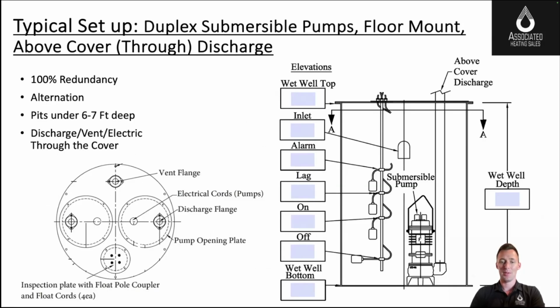Okay. The only other thing I'd like to point out is how these pumps sit. So this is going to be a floor mounted pump with a vertical discharge that's sort of installed on the pump. So when you go to remove this pump, you're removing the pump with a chain up through the pump opening here, and you have a discharge pipe that's quite long that's attached. So this gets us into when we need a rail system. If this pit is deep and we're indoors, so let's say it's 10 or 12 foot deep and we have 8-foot ceilings, removing that pump with this large discharge pipe will be quite difficult.